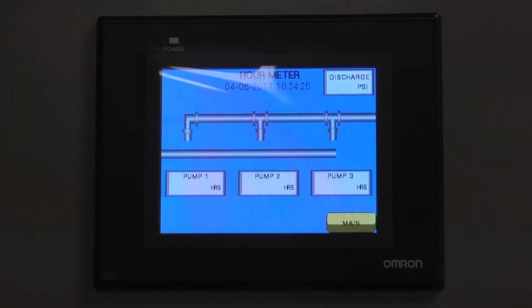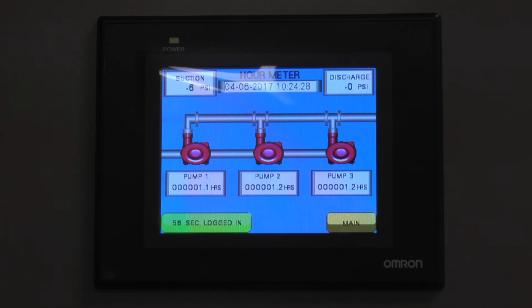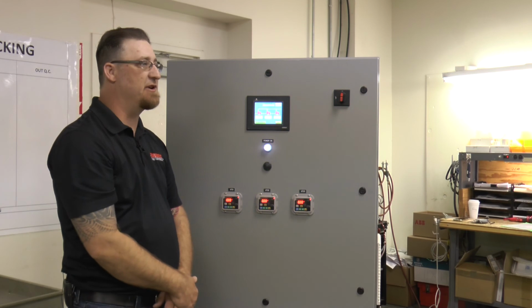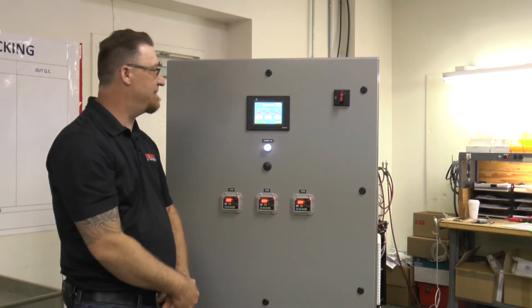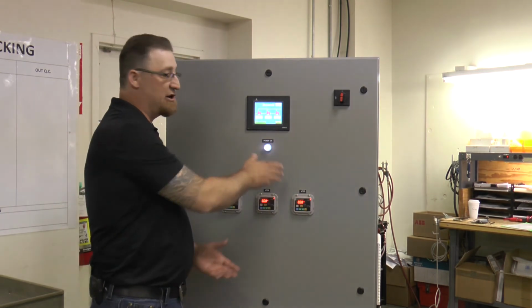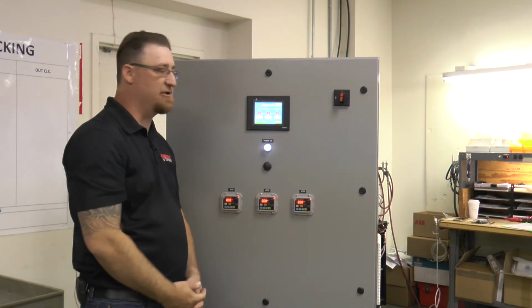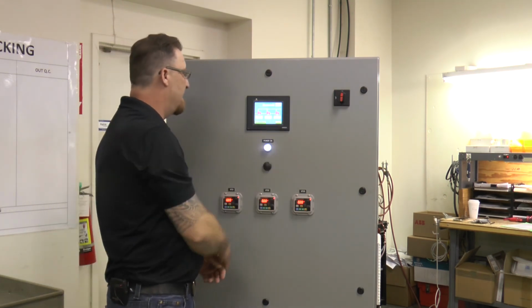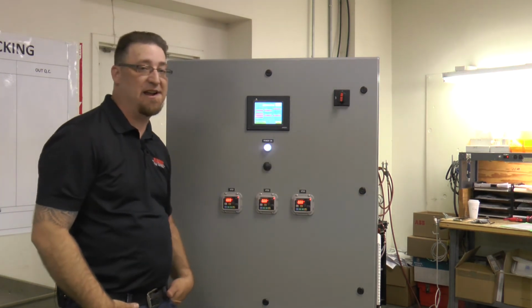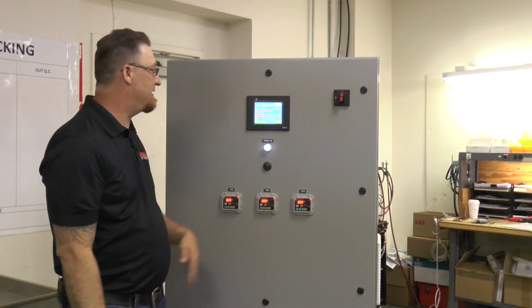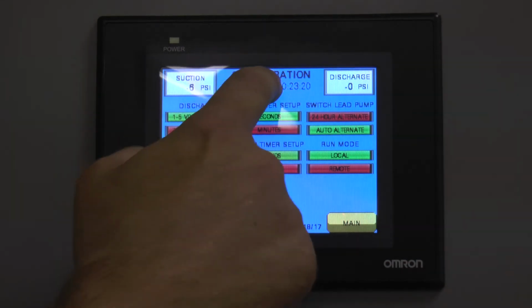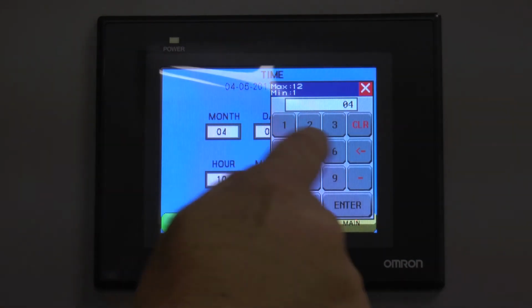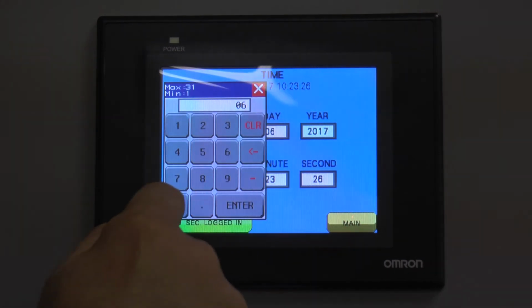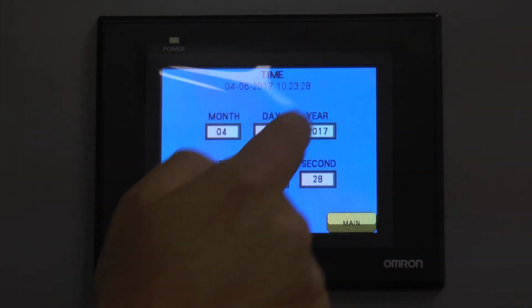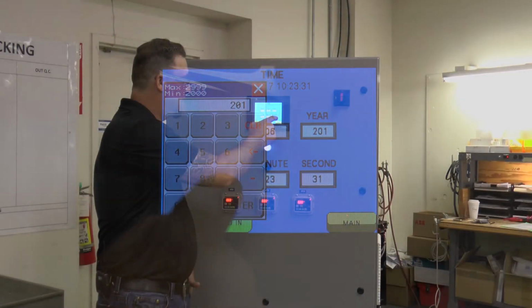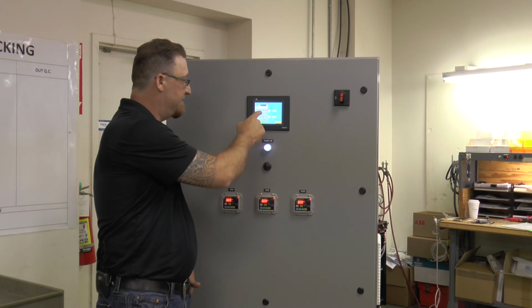We also have an hour meter function. On the hour meters, it lets you know how long each pump has run. So every time one of your pumps comes on, the hour meter starts ticking up. And these are not resettable by the user, or easily, put it that way. And if at any time your date and time is wrong or is not being displayed correctly, you can press the date and time button up here, and you can change those as long as you're logged in. You just press the button, change the month, change the day, and change the year.